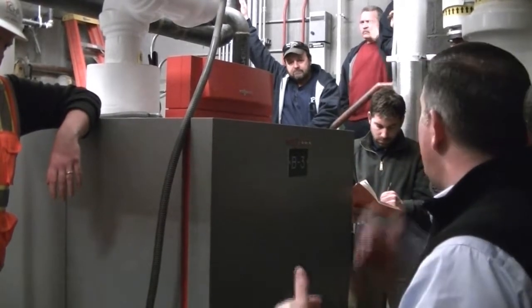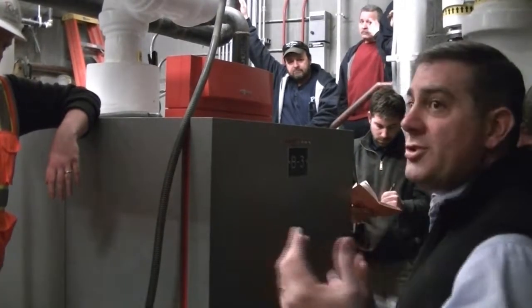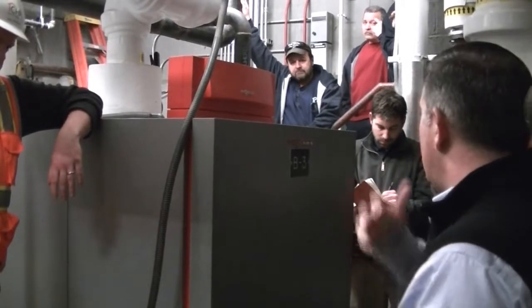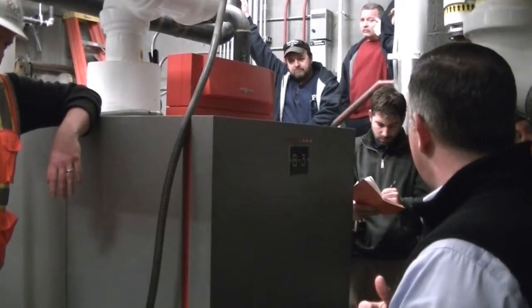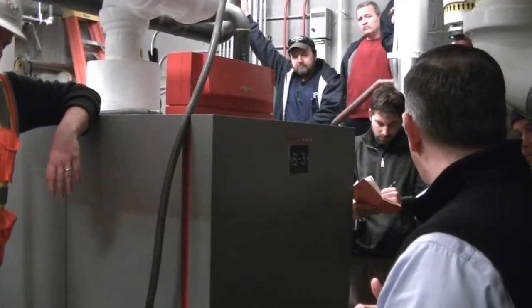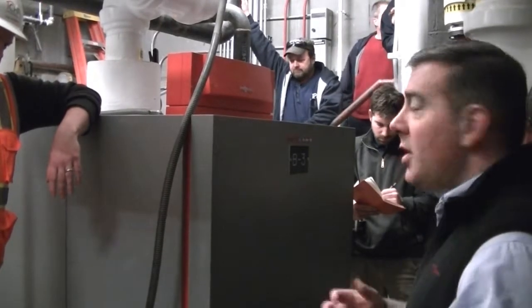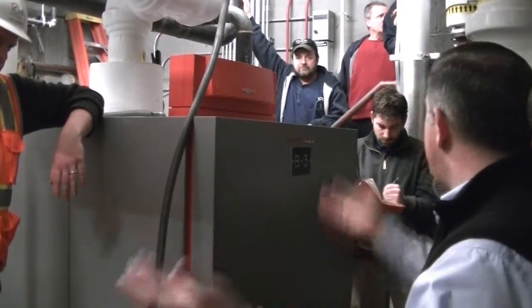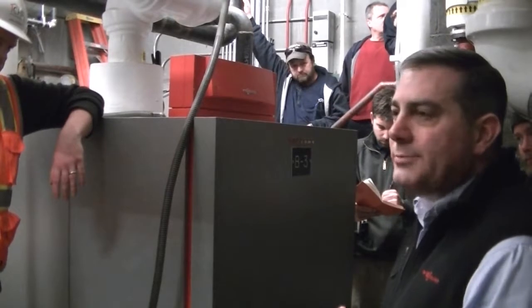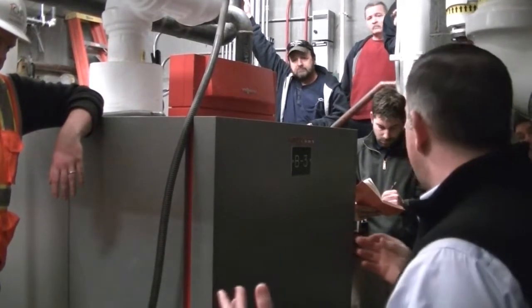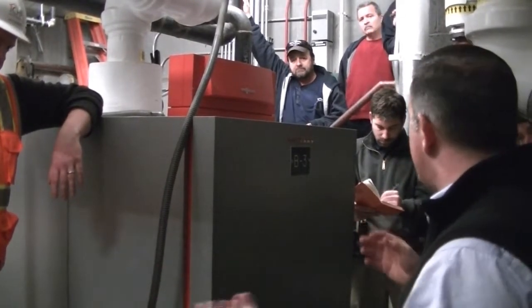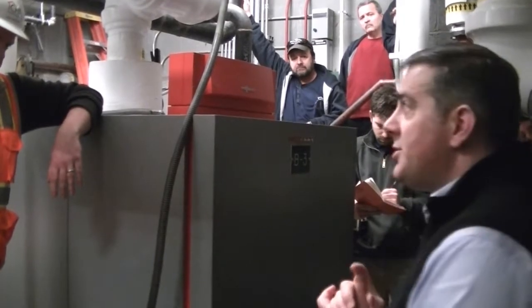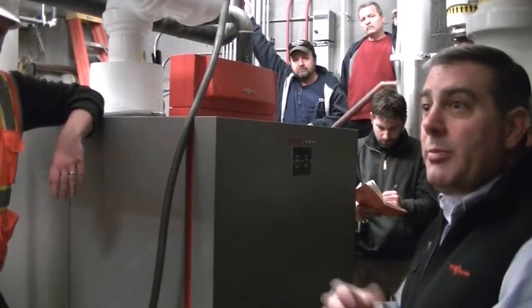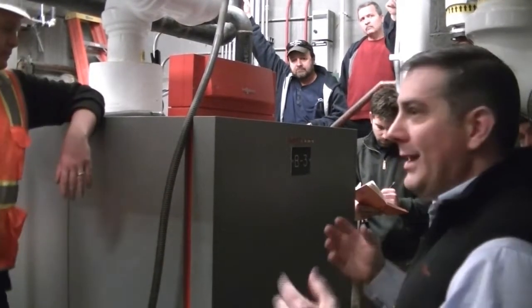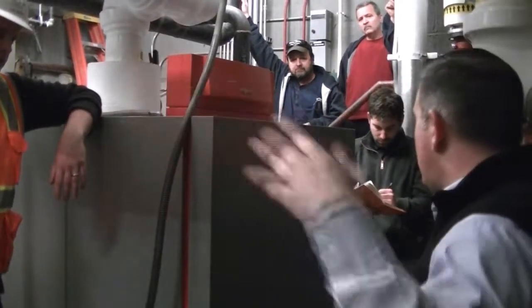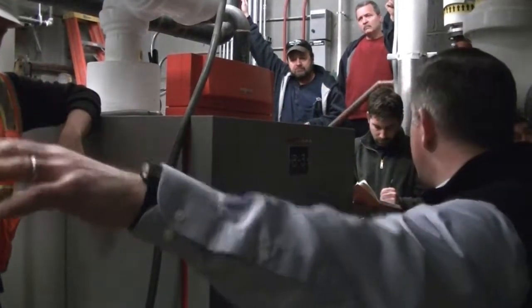That's why you'll see peak or higher efficiencies in your shoulder seasons, or on a day like today, even though we're in the beginning of March and still at 40, 50 degree temperatures outside. At higher outside temperatures, that's when you'll see higher efficiencies in the boilers inside. Now, this system is a little bit different in that, in addition to the 4 boilers, we've also got a cogeneration system outside giving some supplemental heat to the building as well. That is actually being enabled and disabled by a call for heat from our main boiler control.